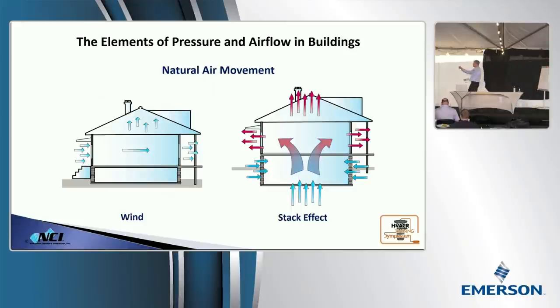On that illustration that you guys can see, those arrows, and this is a very, very simplified illustration of what happens with wind. Wind does all kinds of funky stuff on a building. As you're seeing the arrows moving from left to right, what you're seeing is the windward side of the building. If you have combustion air ducts on that side, air will push into those grills, and that will cause infiltration when the wind's blowing. Now, you guys tell me, what's going to happen on the opposite side? If that wind's still blowing that same direction, and it's coming out the right-hand side, it'll be exiting. Those combustion air grills will actually act as exhaust grills because of pressure difference.